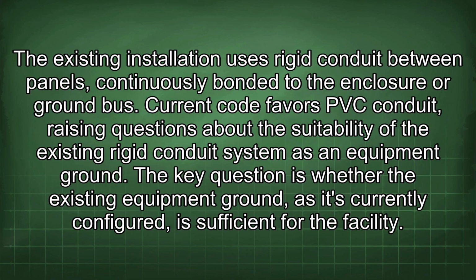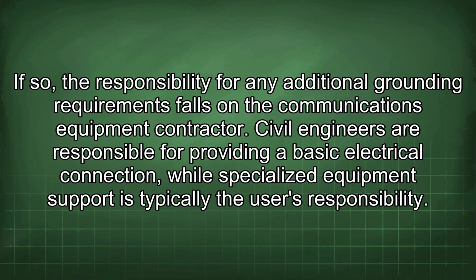The existing installation uses rigid conduit between panels, continuously bonded to the enclosure or ground bus. Current code favors PVC conduit, raising questions about the suitability of the existing rigid conduit system as an equipment ground. The key question is whether the existing equipment ground, as it's currently configured, is sufficient for the facility. If so, the responsibility for any additional grounding requirements falls on the communications equipment contractor.